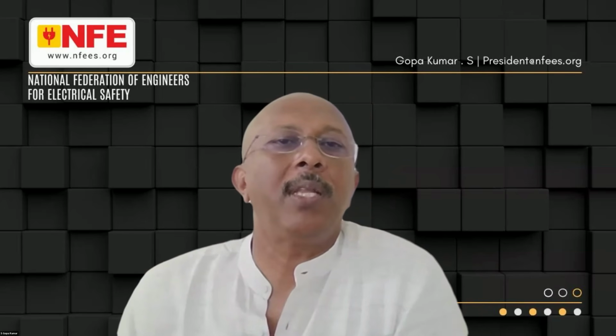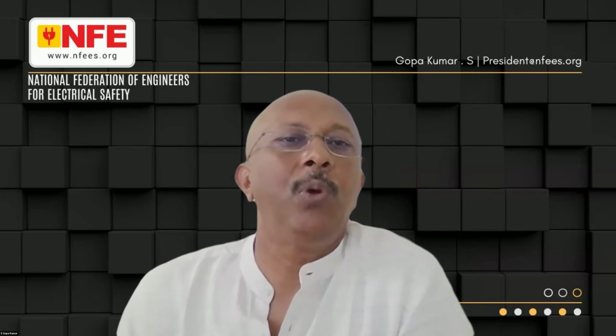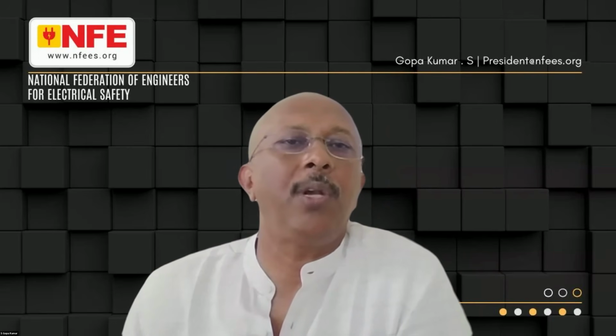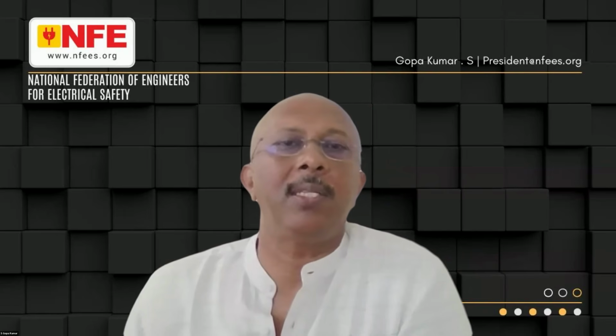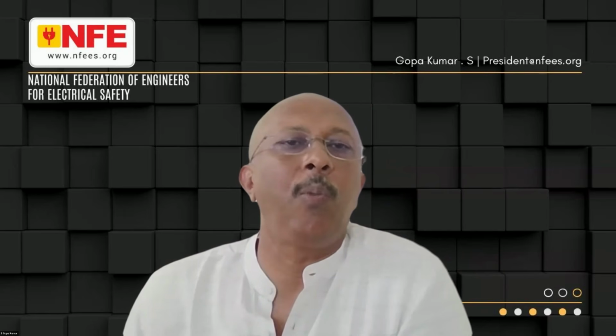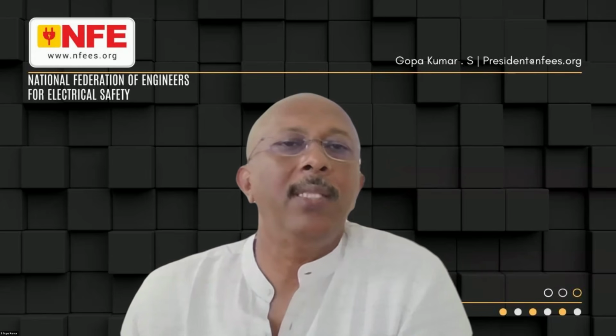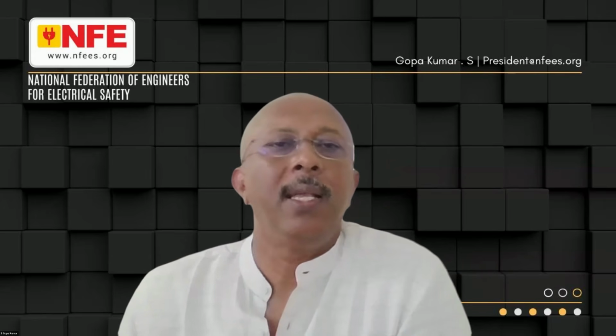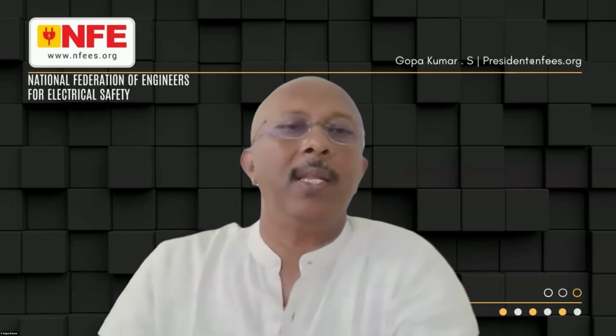Local authority, Mr. Abdul Ghaffur is asking, local authority requirement is earth resistance shall not be more than 1 ohm to achieve. We connect multiple earth electrodes in series. Is it correct? It is wrong. It is not correct. It is wrong.